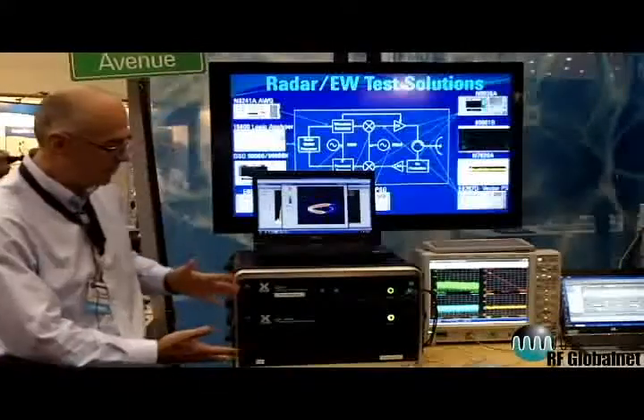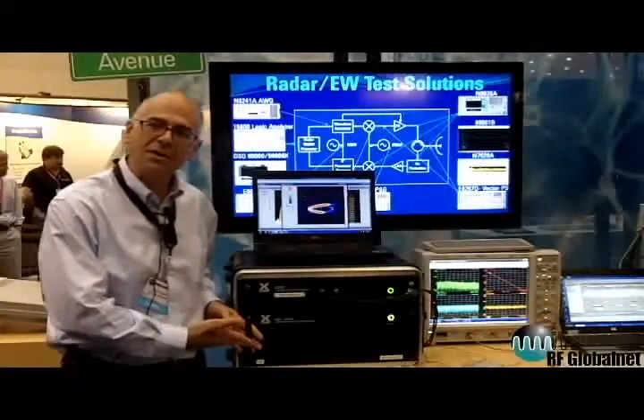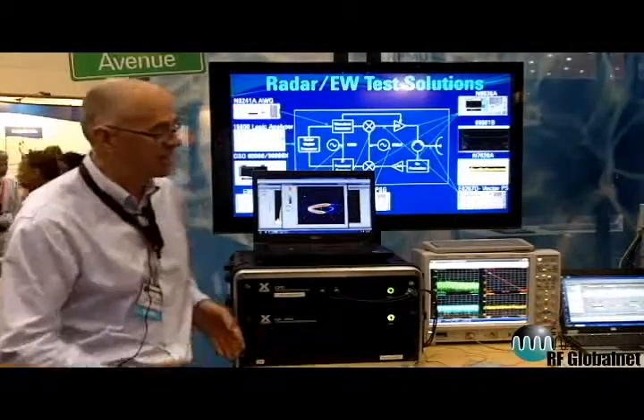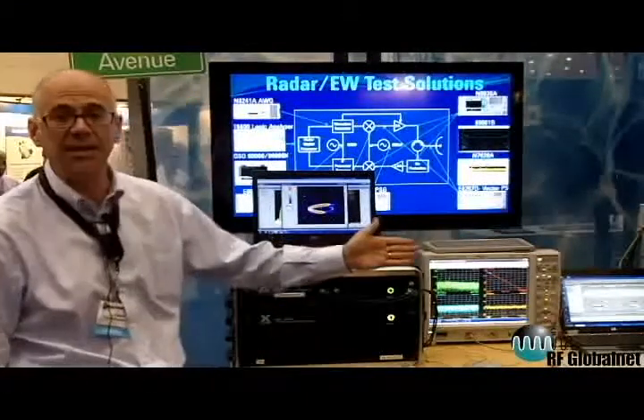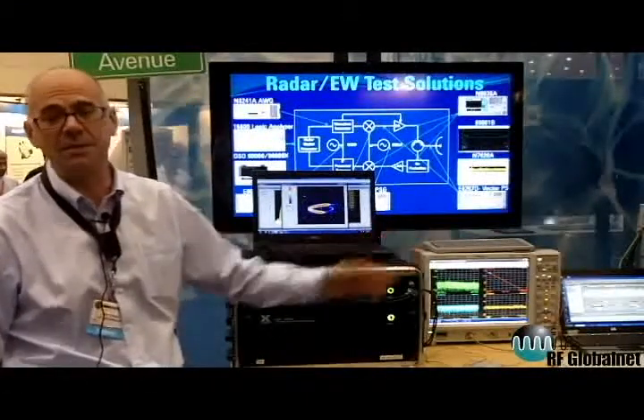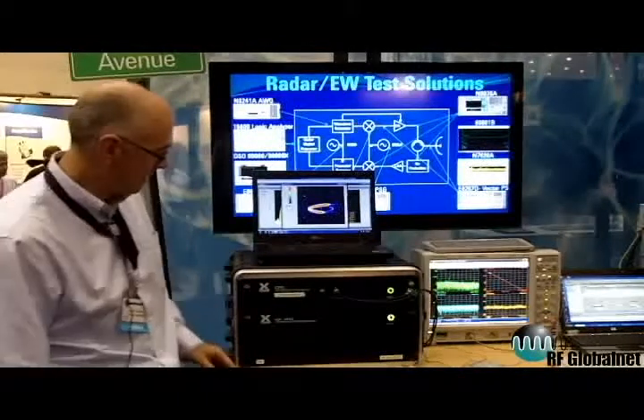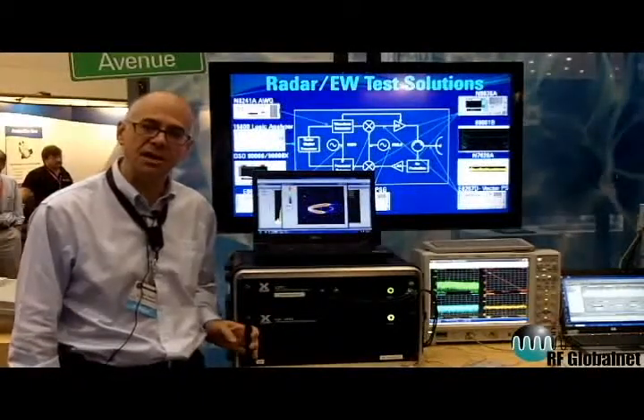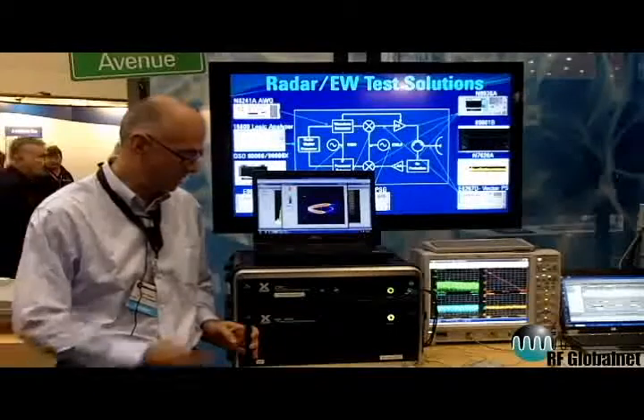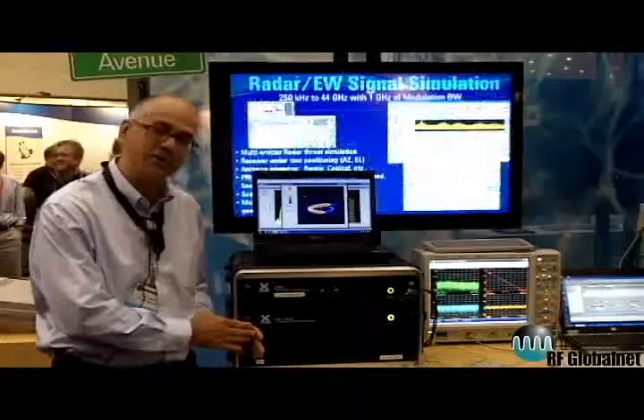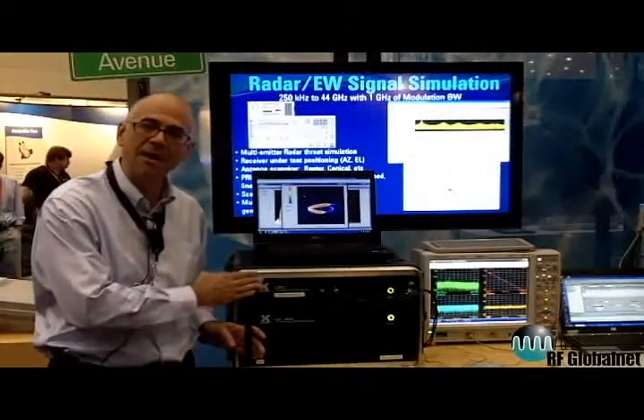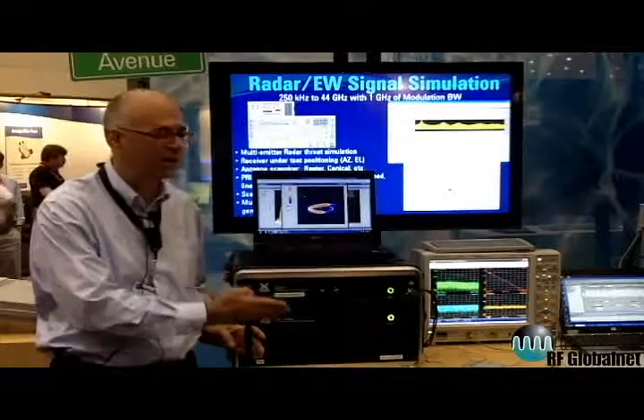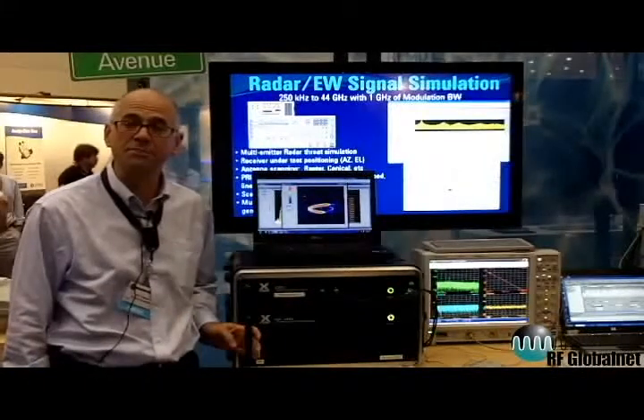So in summary, we have a 40 megahertz signal capture solution that can extend up to 50 gigahertz with the PXA signal analyzer, that can capture hours and days of continuous coverage with the XCOM recorder. Once recorded, I can play it back at the same carrier or any carrier that the PSG supports.